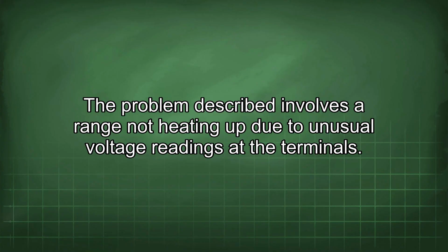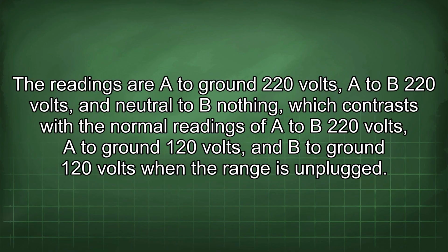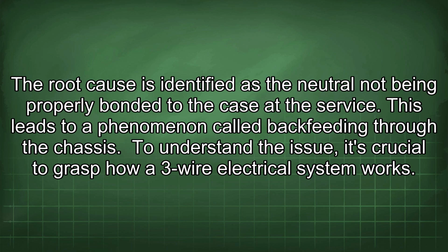The problem described involves a range not heating up due to unusual voltage readings at the terminals. The readings are A to ground 220 volts, A to B 220 volts, and neutral to B nothing, which contrasts with the normal readings of A to B 220 volts, A to ground 120 volts, and B to ground 120 volts when the range is unplugged. The root cause is identified as the neutral not being properly bonded to the case at the service. This leads to a phenomenon called backfeeding through the chassis.